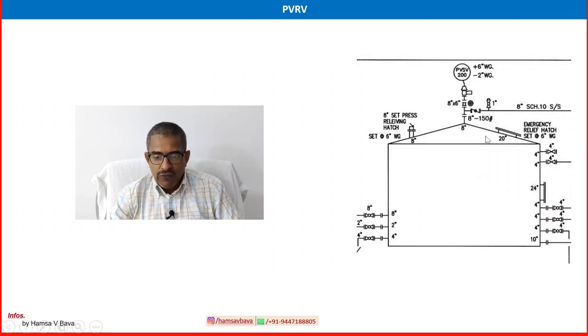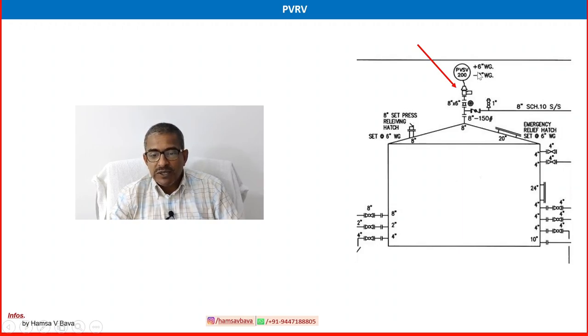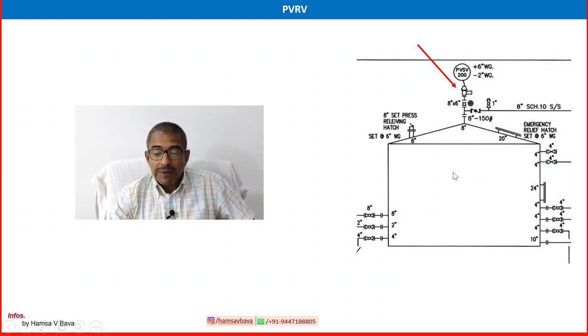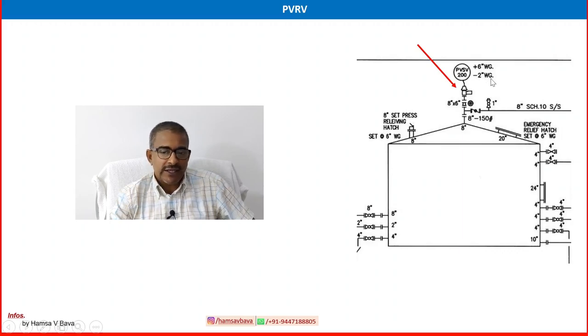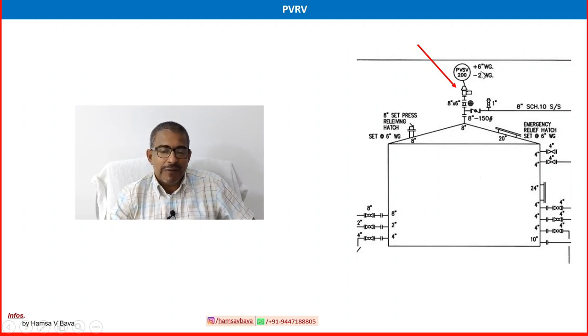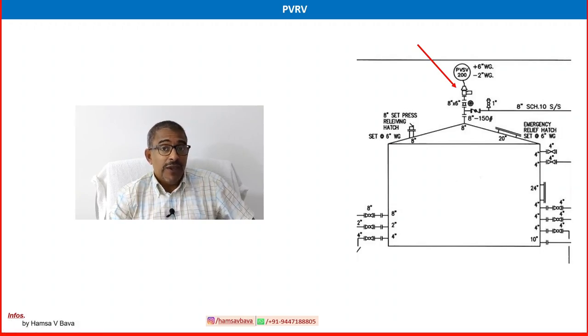Here is a P&ID of a simple storage tank showing a PVSV. Unlike a regular PSV which has only one set point, here you can see two set points: a positive set point of +6 inches water gauge for overpressure protection, and a vacuum set point of −2 inches water gauge for under-pressure protection. The pressures are expressed in inches water gauge because the system operates near atmospheric pressure — very low pressures of around 1–2 PSI. You can refer to your P&ID and visit the field to identify and familiarize yourself with the equipment.